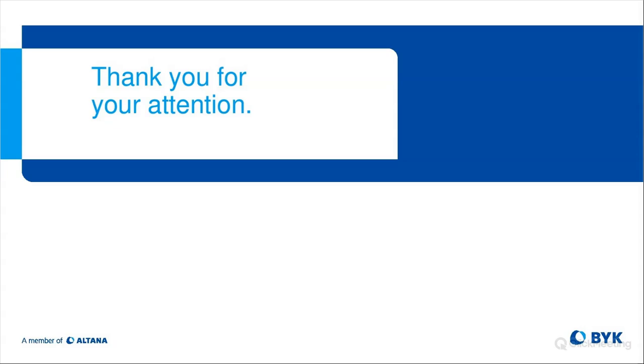Nice. Is there a maximum number of layers that can be measured simultaneously? Right now, the calibration limit is 5 layers. However, if you have several repaints all in a row, we can always give you a total thickness. And if there's a specific combination you want calibrated, as long as it's up to 5, we can combine a couple of those layers. But we can open up that window and we can measure a total film build for quite a few layers. You're going to see every echo. We can only calibrate; you only get markers for up to 5.